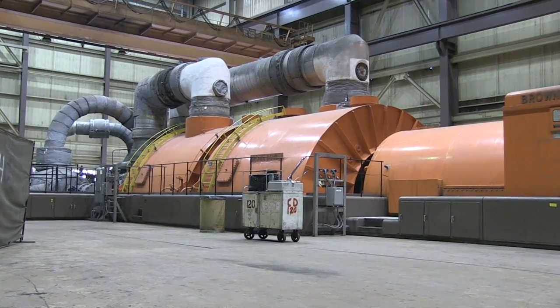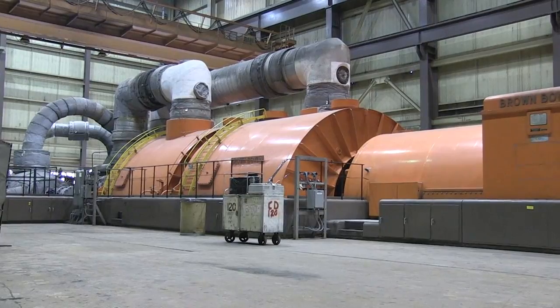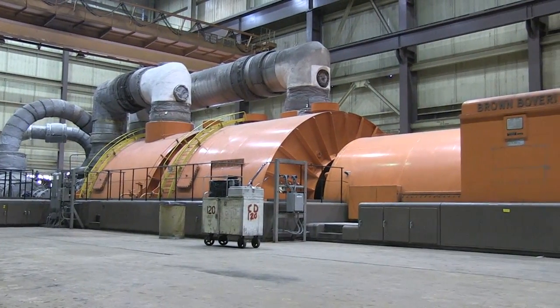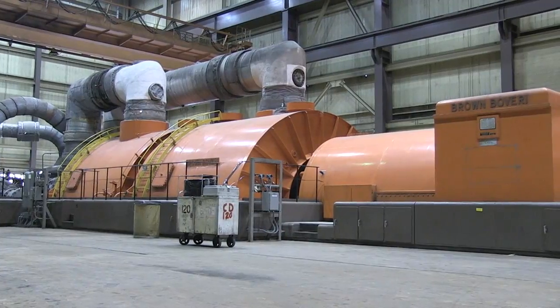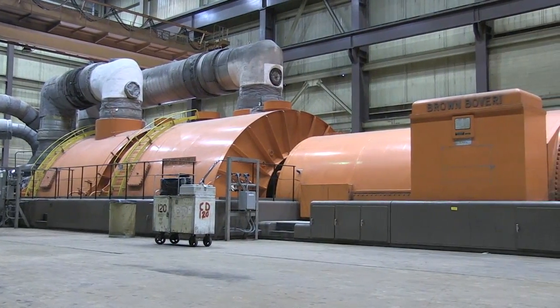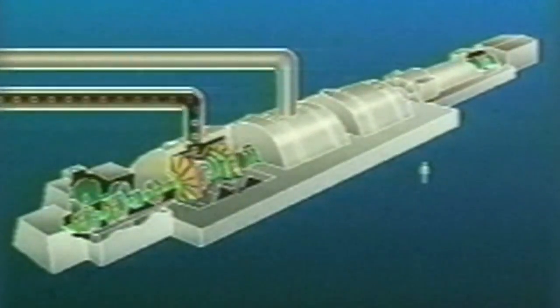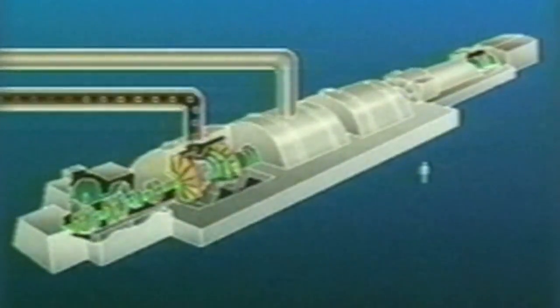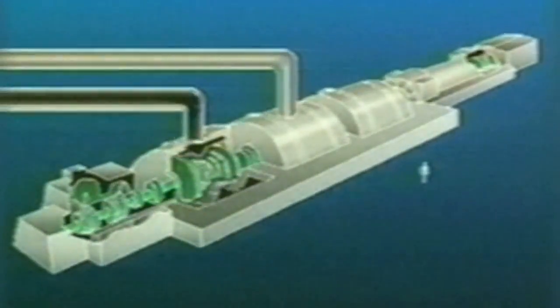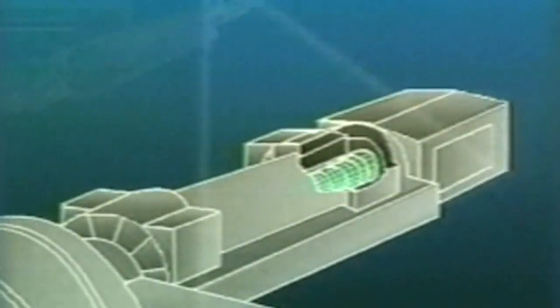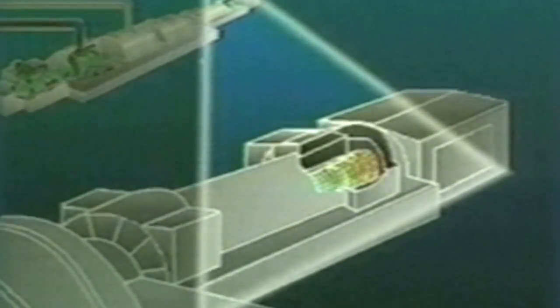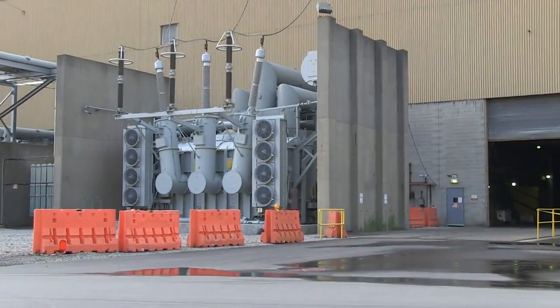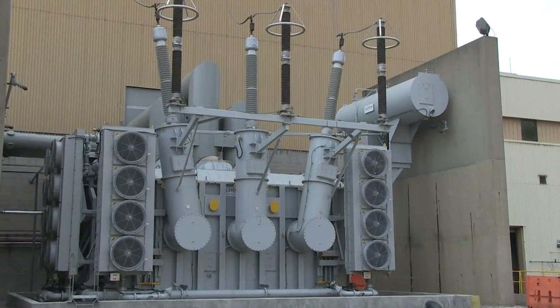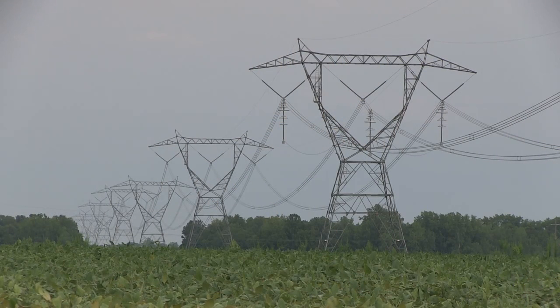High-pressure, high-temperature steam from the boiler is directed into the turbine generator through pipes that are wrapped heavily with insulation. Inside those orange housings at left, the turbine is connected by a shaft to the electric generator. As steam hits the turbine blades, the shaft turns the generator's rotor at 3,600 revolutions per minute. Inside the generator, the rotor turns, rotating an electromagnetic field. That produces electrical power at 26,000 volts. That power goes through a transformer and is stepped up to 345,000 volts, then sent out on transmission lines to consumers across the state.